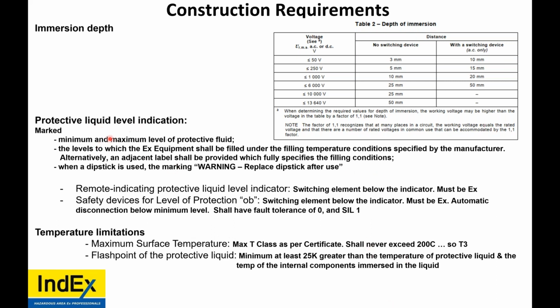Now, protective liquid level indication. It needs to be marked with the minimum and maximum levels of protective fluid allowed. Think of your car, your oil, if you do an oil change, what's the maximum amount in liters of oil you're allowed and the minimum amount. Now, the levels at which the EX equipment shall be filled under filling temperature conditions specified by the manufacturer. Can you fill this at 50 degrees Celsius or when it's minus 40? Read the IOMs. When a dipstick is used, the marking, warning, replace after use shall be there.